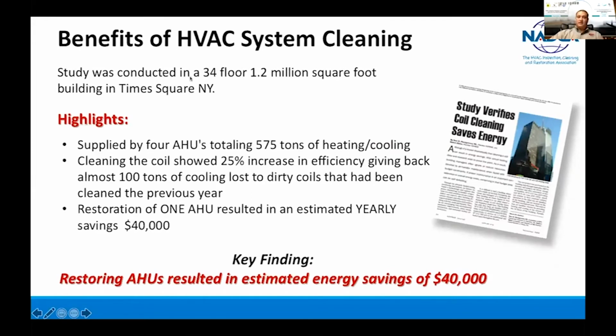The study was conducted in a 34-floor, 1.2 million square foot building in Times Square, New York, supplied by four air handling units totaling 575 tons of heating and cooling. Cleaning the coil showed a 25% increase in efficiency, giving back almost 100 tons of cooling lost to dirty coils that had been cleaned the previous year.